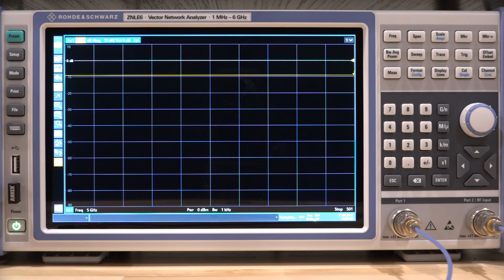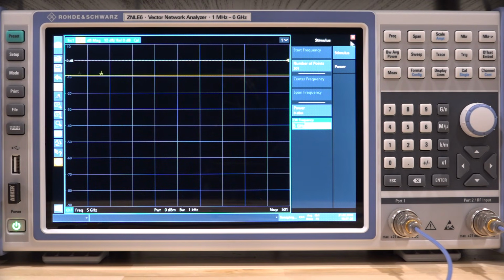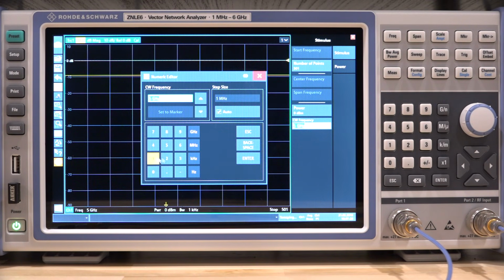The reason this is a problem for CW mode is that if you want to use this as a synthesizer, then at frequencies above 4 gigahertz or so, every time this reaches the end of the screen, you would lose the signal, because then the incident power will be on port 2. I'm sure this can be easily fixed with the firmware, and hopefully they will make that change. But for our purposes, we can still use it without an issue. So let's go ahead and put the frequency back at 1 gigahertz, and my spectrum analyzer is almost ready.